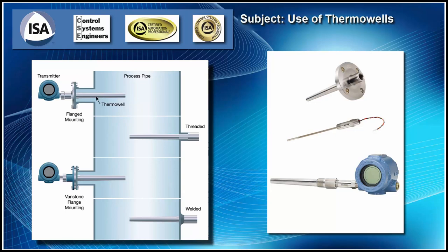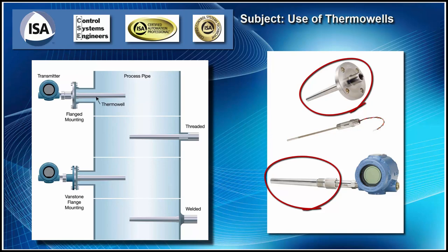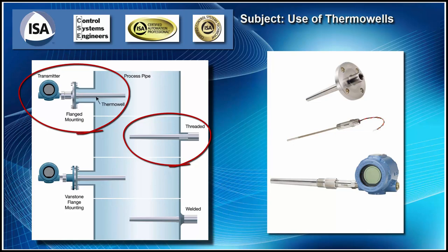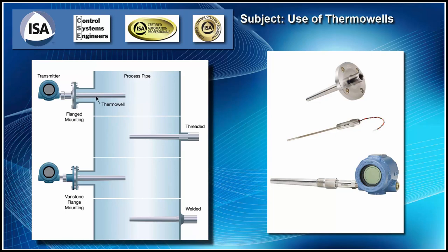Now in industrial processes, typically these thermocouples and RTDs go into what's called a thermowell. And what this is, while the process is running, say the thermocouple or the RTD fails on you, you need to be able to pull this out and replace it. So if we didn't have these thermowells, our process fluid would squirt out everywhere, or we'd have to shut down our process. So the thermowell gives you a hole. It's basically just a deep little hole, just like drilling a well. It's a hole going down inside the process pipe, and it isolates the thermocouple from the process.